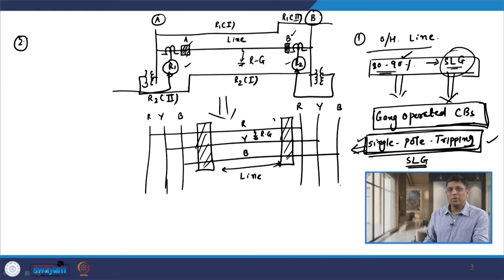The second thing is that if I consider the second problem of distance relays, then we note that if I consider again the overhead line or conductors, then whatever faults occur on this overhead conductor, again 80% of faults are transient in nature. The meaning of transient in nature is that this type of fault may die down after maybe 1 or 2 cycles or maybe 3 cycles, it depends on the type of fault.